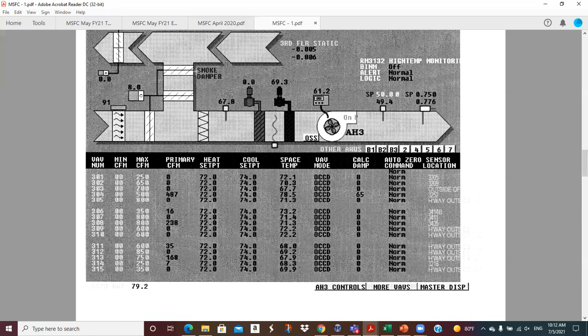This is a smoke damper. So if they weren't going to purge the thing, then this would close and everything would be sucked out, I guess. We've got a couple coils here. This is 0, so I'm guessing this is a hot water coil. And then this is a chill water coil, but I'm not sure.